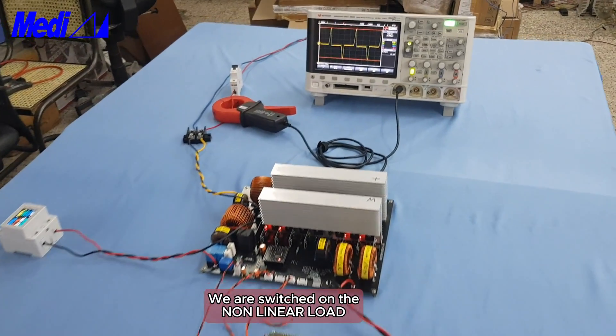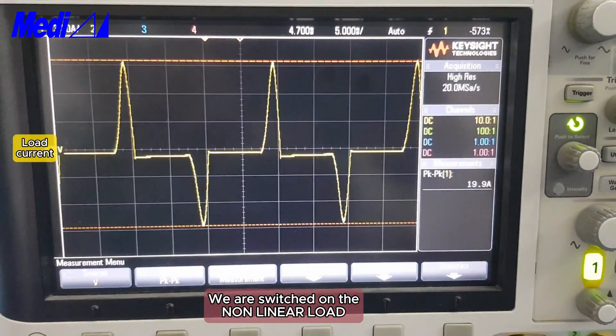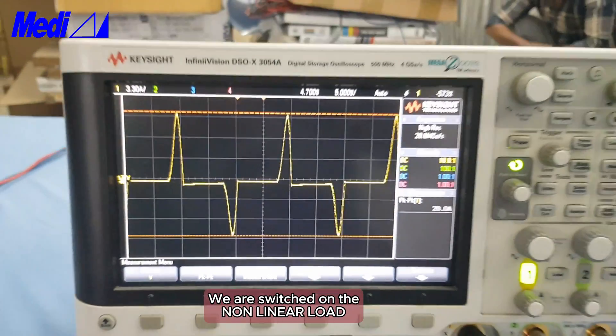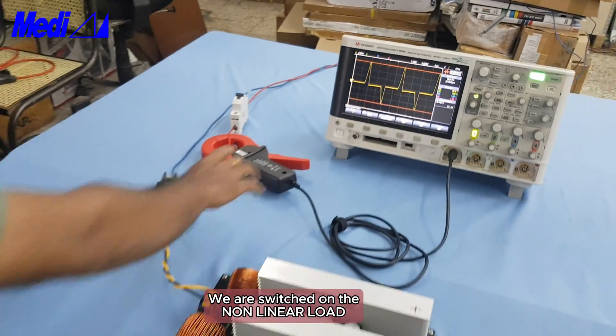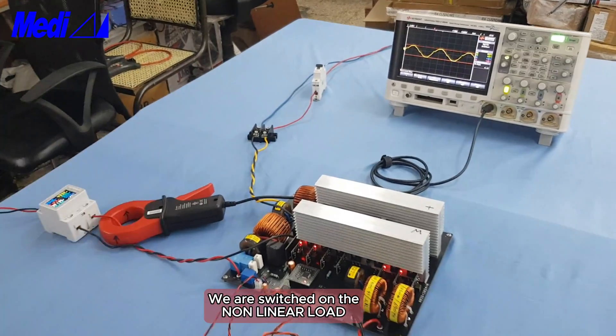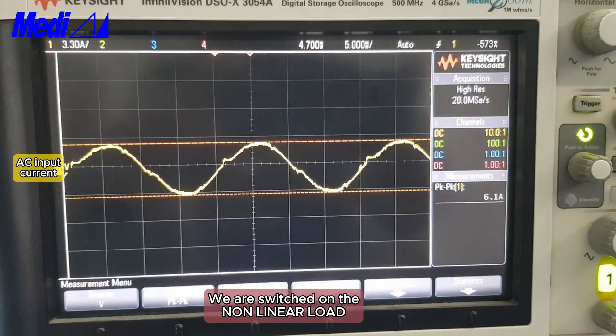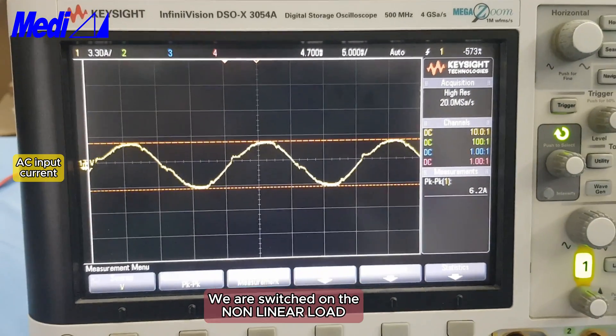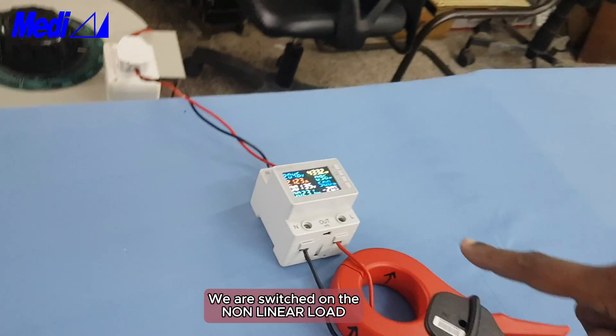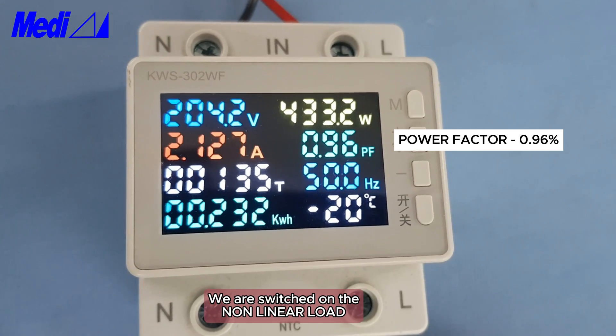We are switching on the non-linear load — this has very high current harmonics at 20 ampere peak-to-peak. Now changing the current meter to the input: you can see the current came down to only 6.1 ampere, power factor improved, and current harmonics also came down. Power factor improved to 0.96 and harmonics reduced to 3 percent.